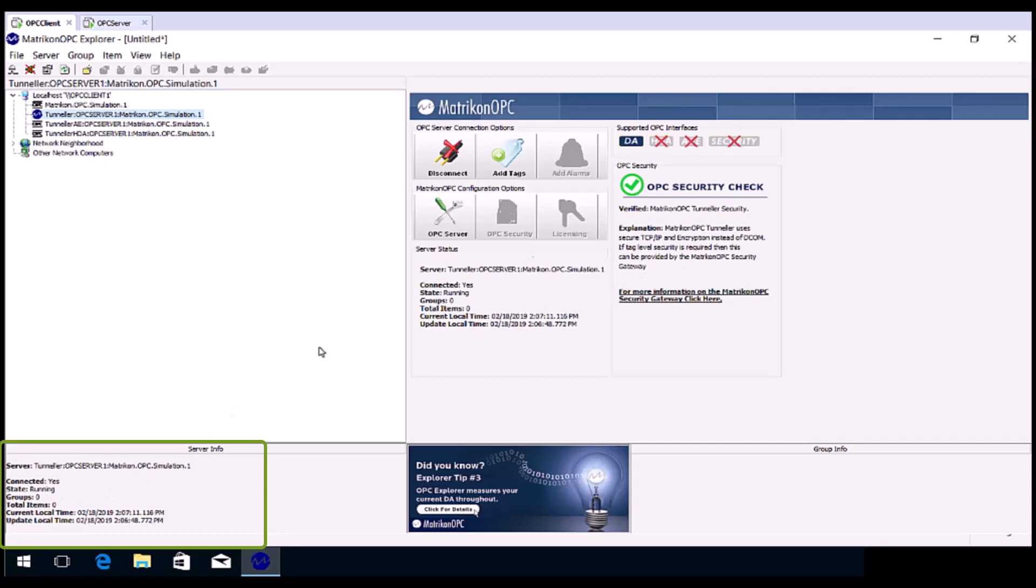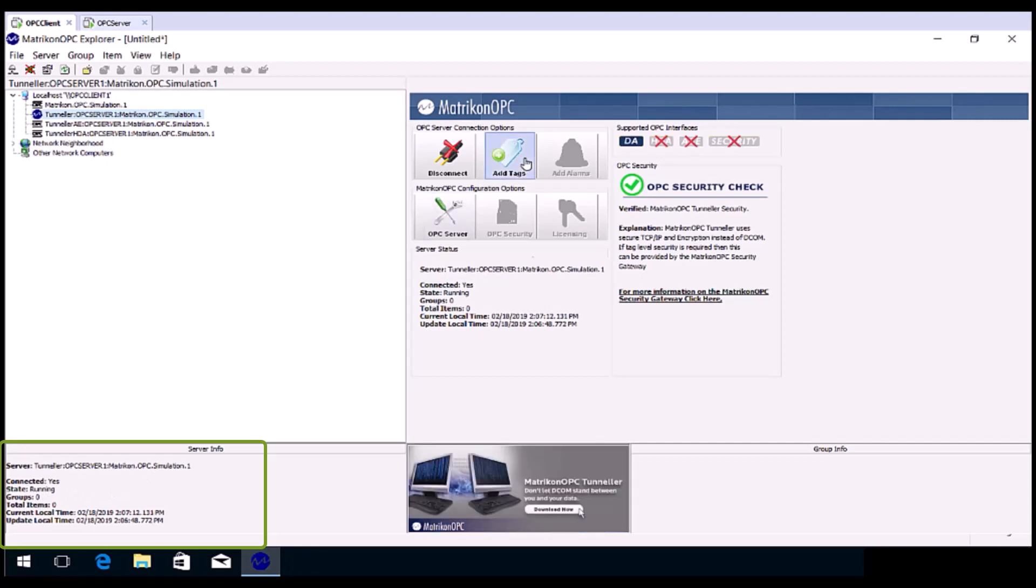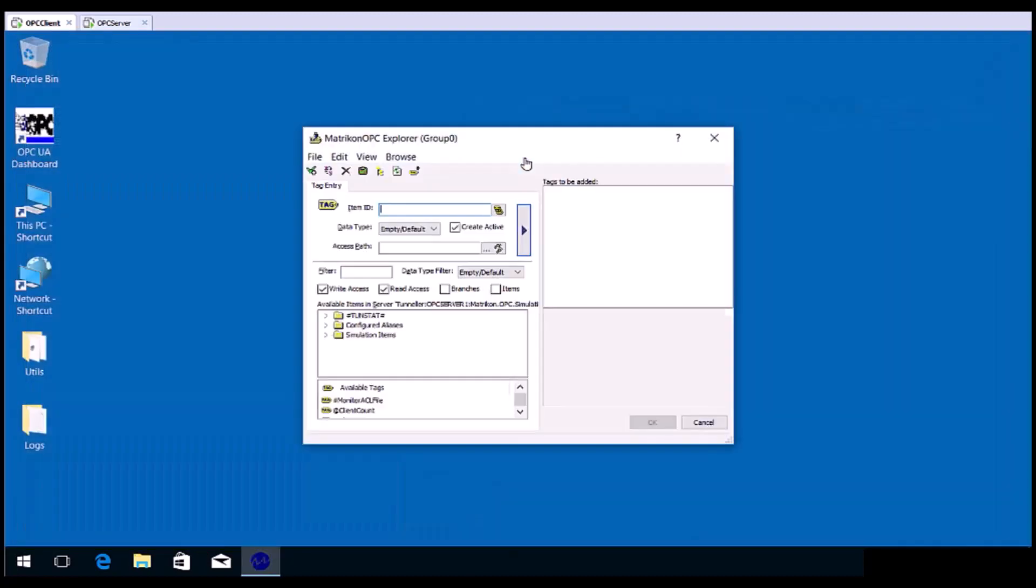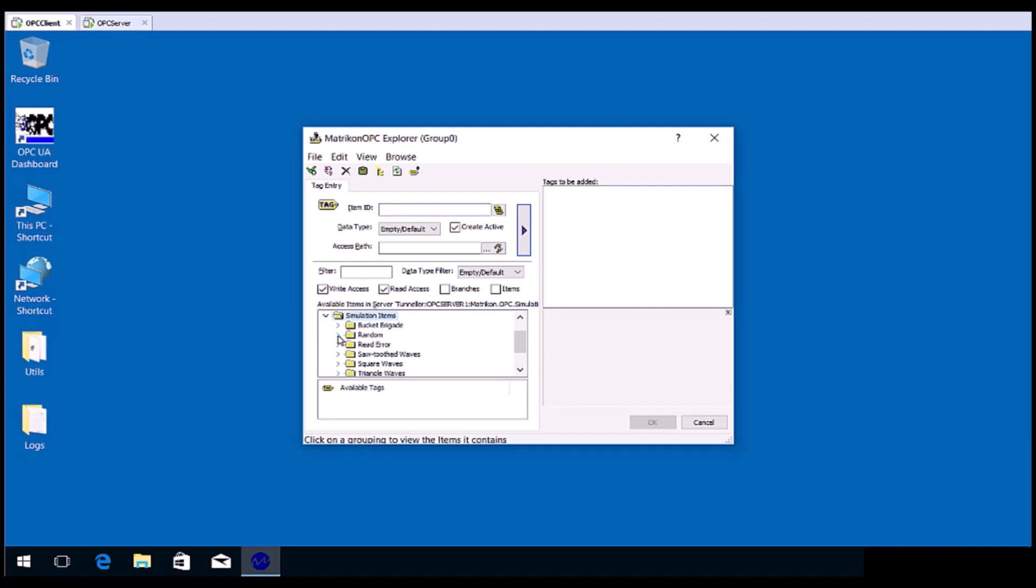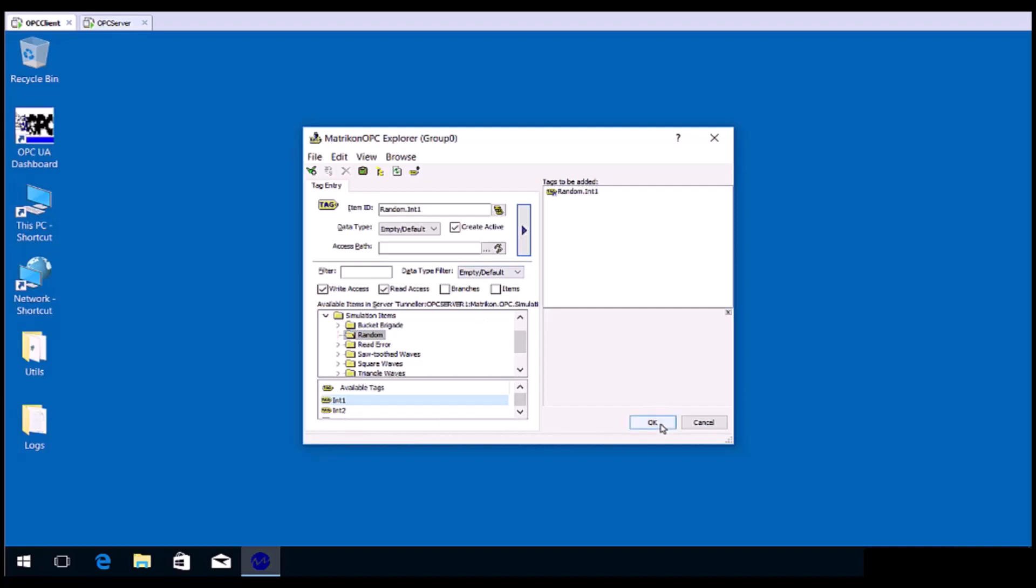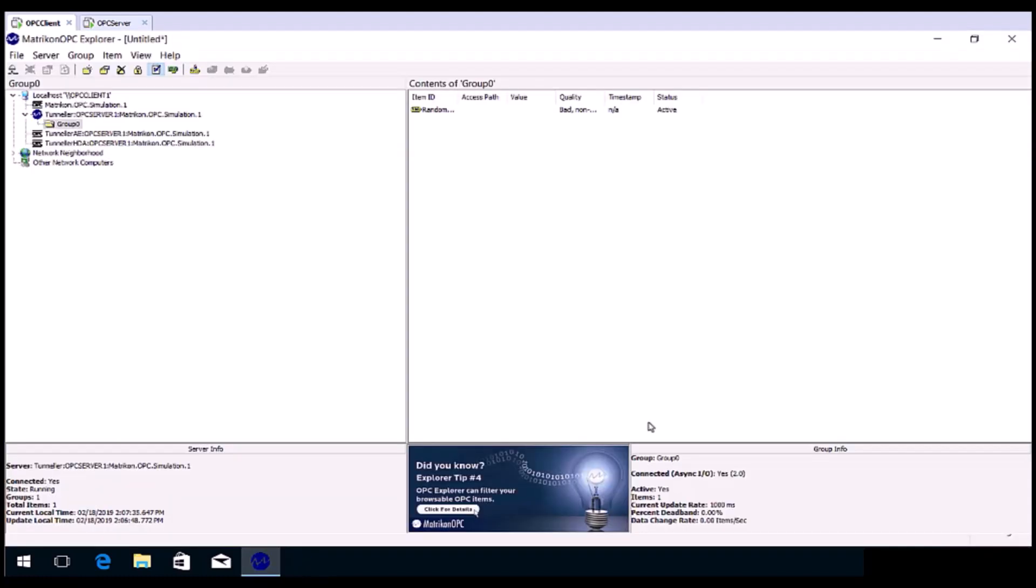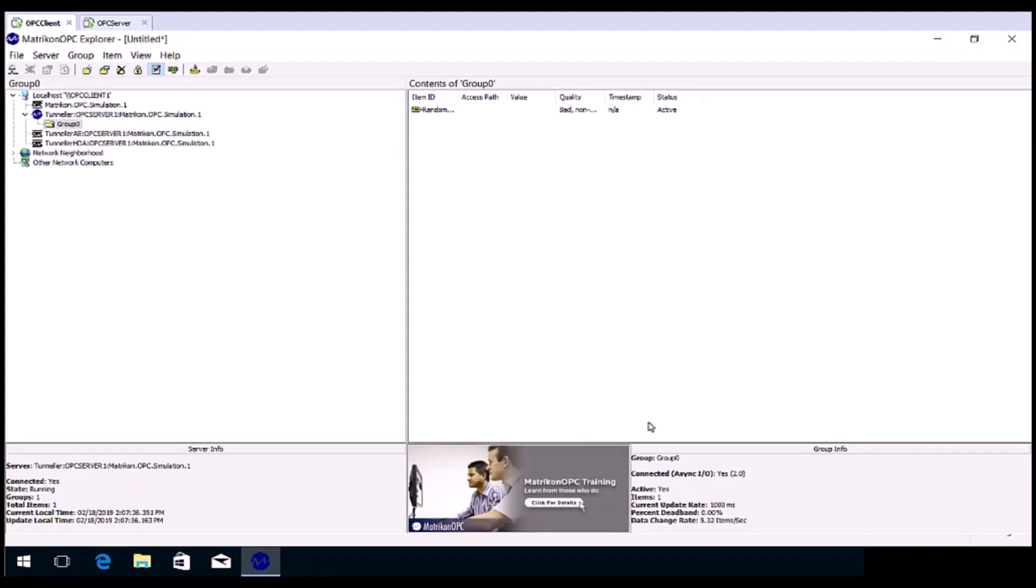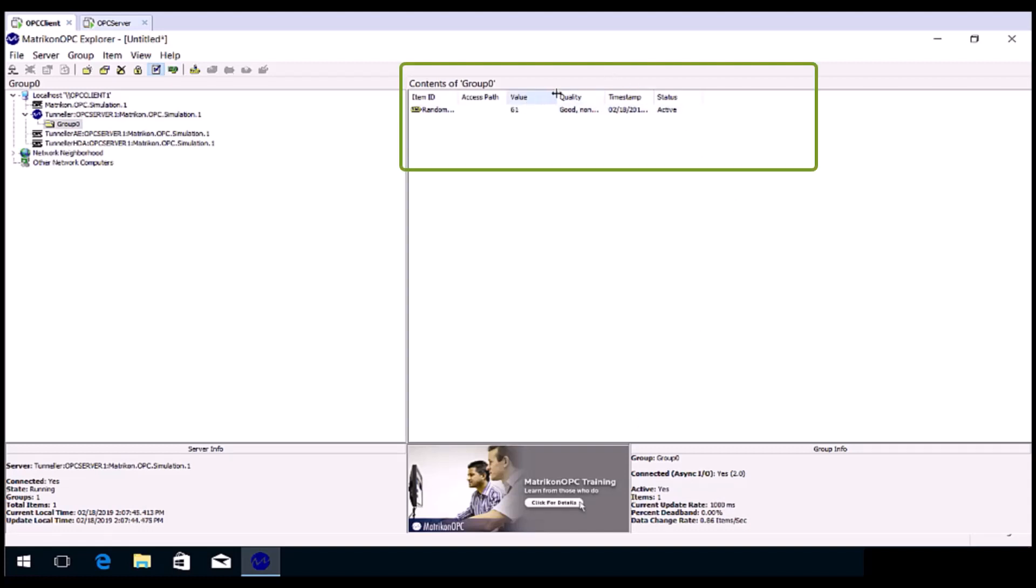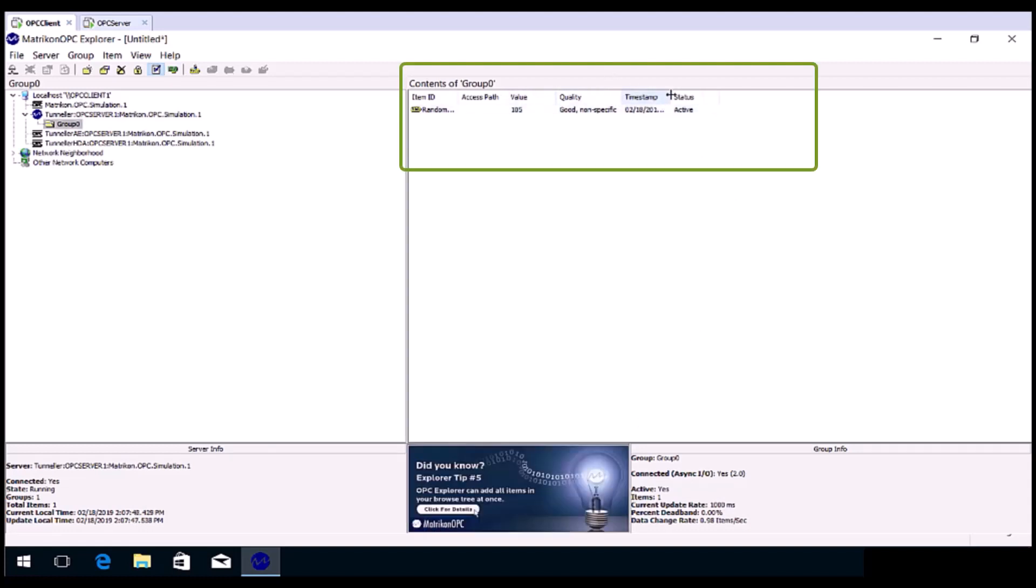You'll be able to see that your tags on your remote OPC server are now available. Go ahead and double-click a tag to add it to the right-hand side, Tags to be added area, and click OK. You should see good quality with changing values, assuming the tag that you chose is updating.